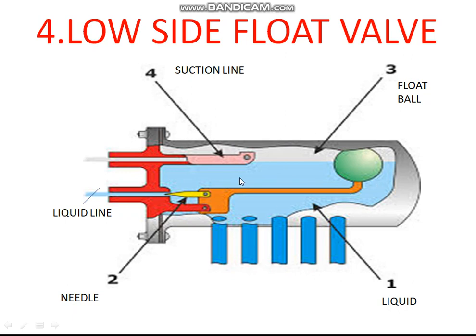How is the float valve working? When the liquid level is low, the float valve drops down and the needle valve opens, allowing refrigerant liquid to flow in. The liquid level in the evaporator is maintained by the low side float valve.